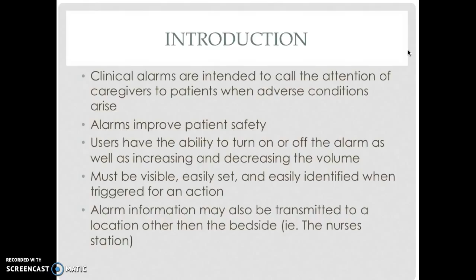Introduction. Clinical alarms are intended to call the attention of caregivers to patients when adverse conditions arise. Alarms improve patient safety. Users have the ability to turn the alarms on or off, as well as increase and decrease the volume of the alarms. Alarms must be visible, easily set, and easily identified when triggered for an action. Alarm information may also be transmitted to a location other than the bedside, such as the nurse's station.